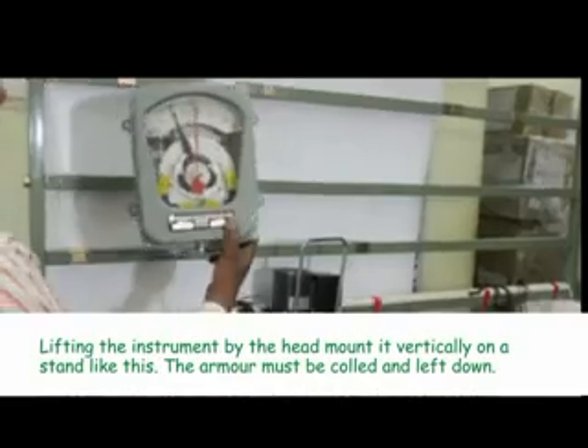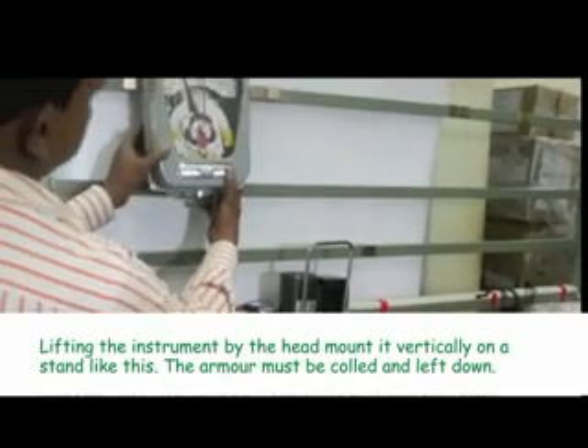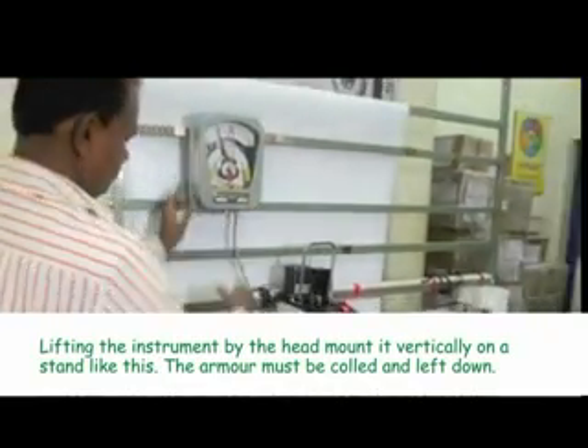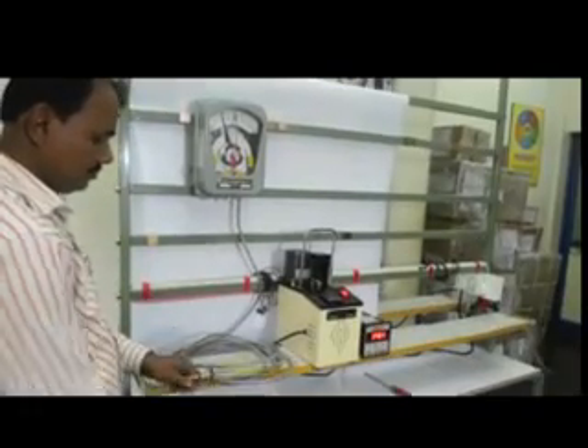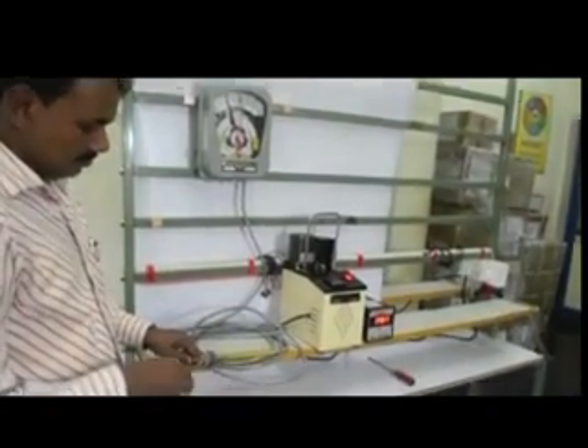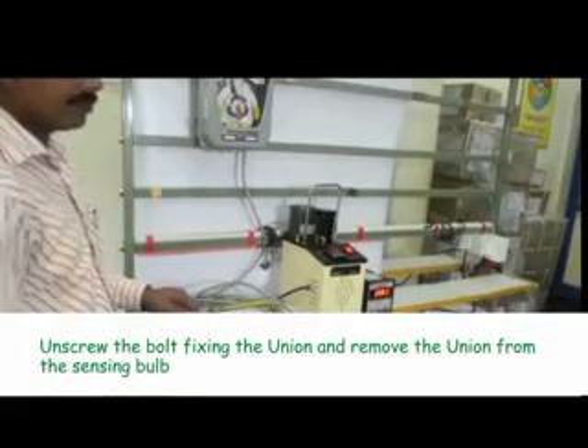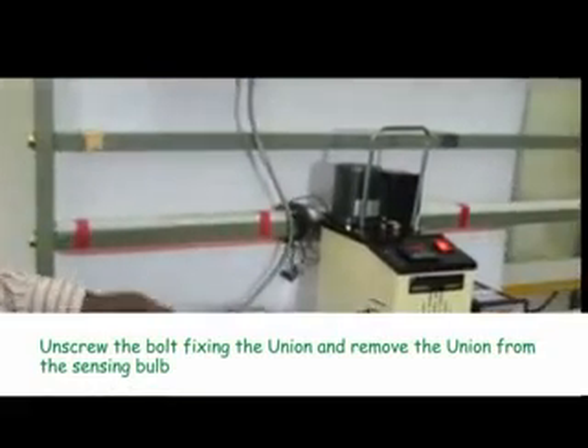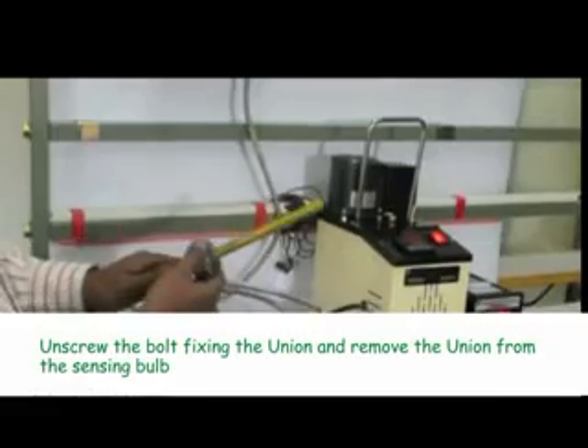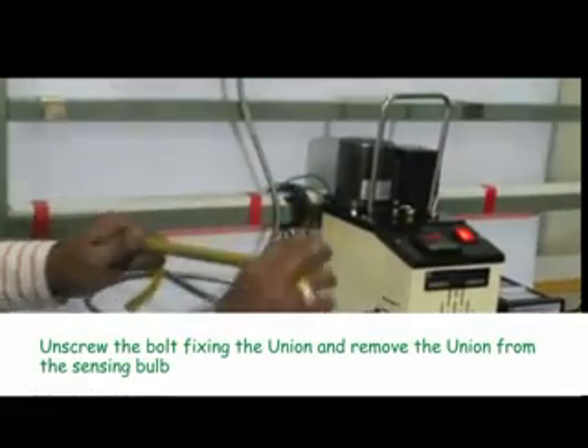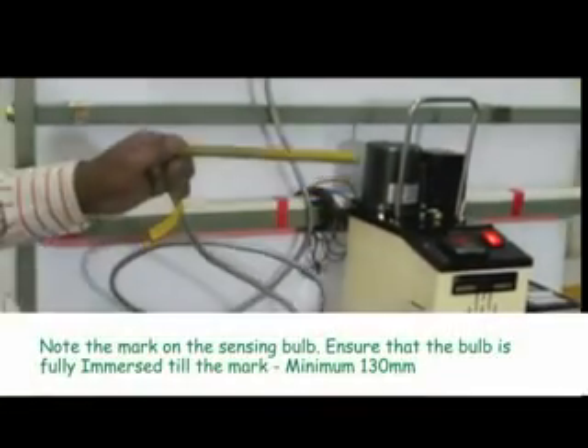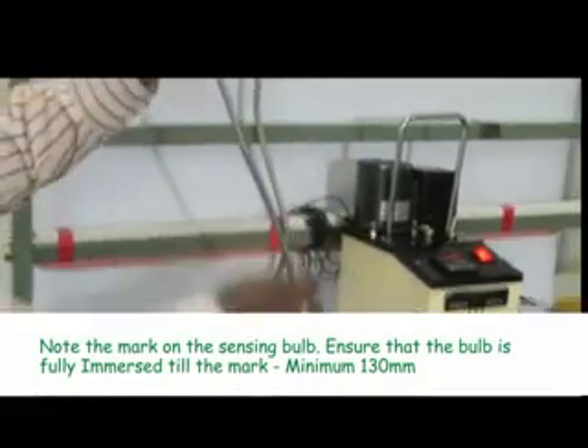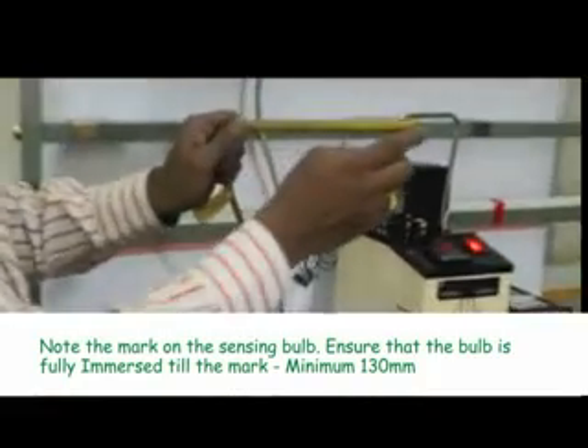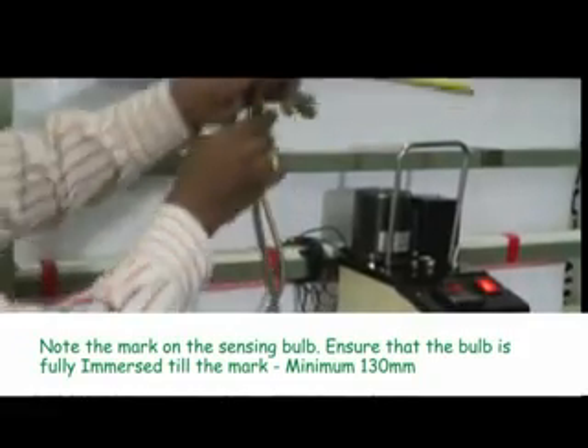Preliminary test procedure. Lifting the instrument by the head, mount it vertically on a stand like this. The armor must be coiled and left down. Unscrew the bolt fixing the union and remove the union from the sensing bulb. Note the mark on the sensing bulb. Ensure that the bulb is fully immersed till the mark, minimum 130 mm.